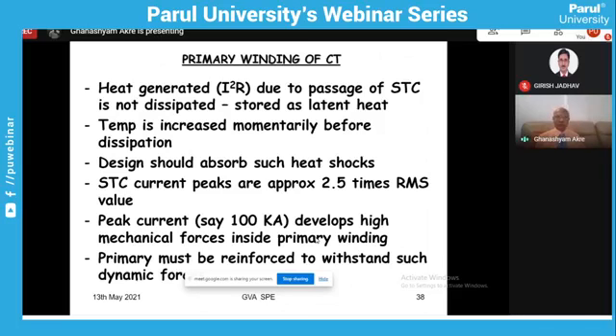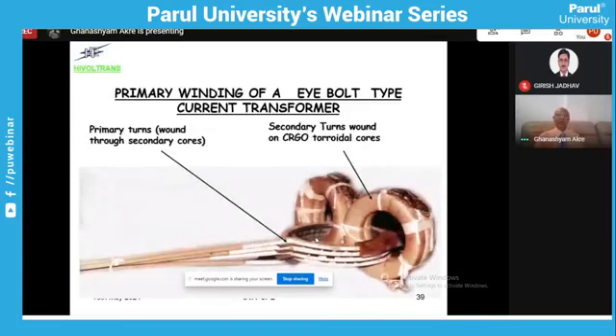So the RMS value is 40 kiloamperes. Naturally, its peak value, or the dynamic value, will be 100 kiloamperes. That will produce very, very high mechanical forces. And if the transformer is not designed properly or the primaries are not properly reinforced, they will fly off or they will get damaged.